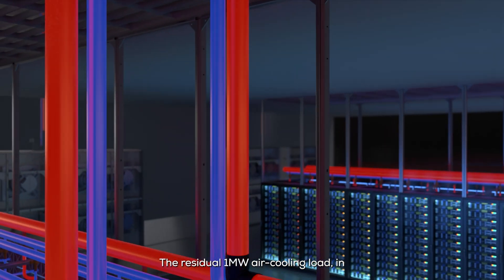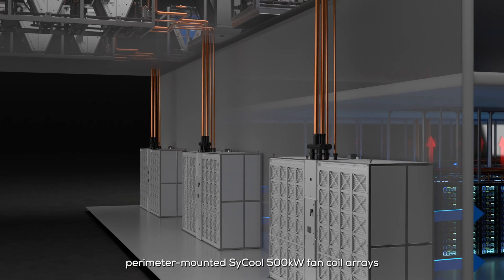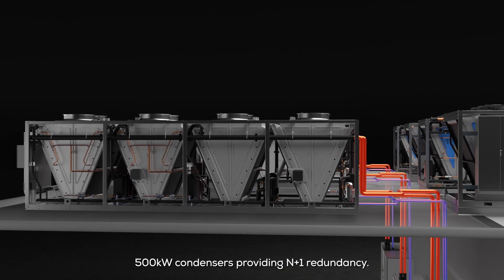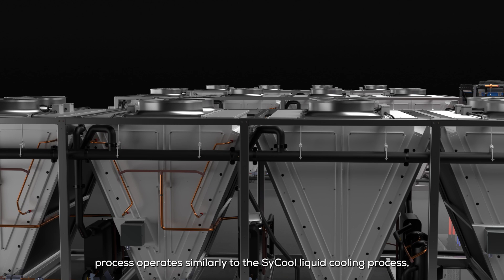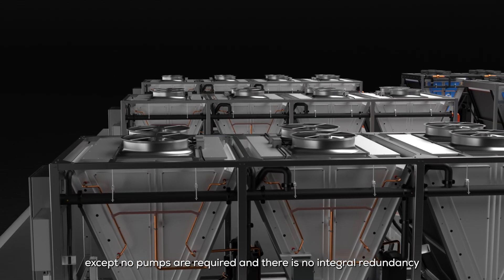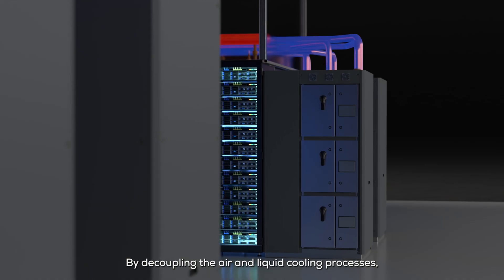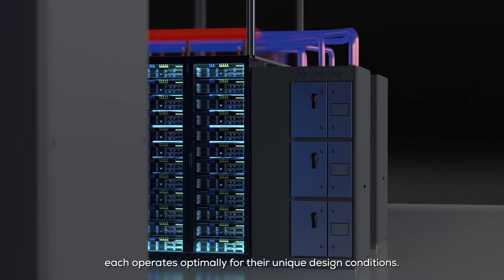The residual 1 megawatt air cooling load, in this example, is managed by three Munters perimeter-mounted SyCool 500 kilowatt fan coil arrays that connect with mating roof-mounted 500 kilowatt condensers, providing N+1 redundancy. This thermosyphon-based heat rejection process operates similarly to the SyCool liquid cooling process, except no pumps are required and there is no integral redundancy within the fan arrays or condensers. By decoupling the air and liquid cooling processes, each operates optimally for their unique design conditions.